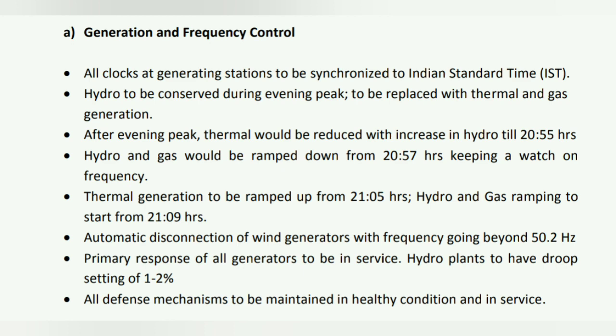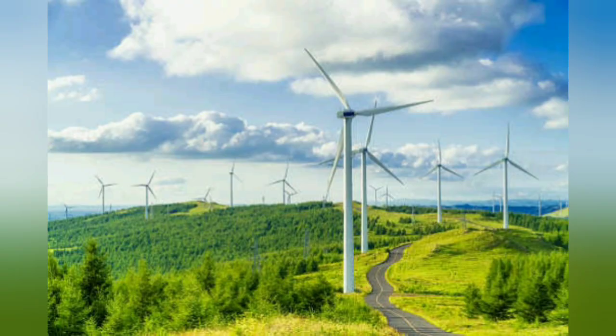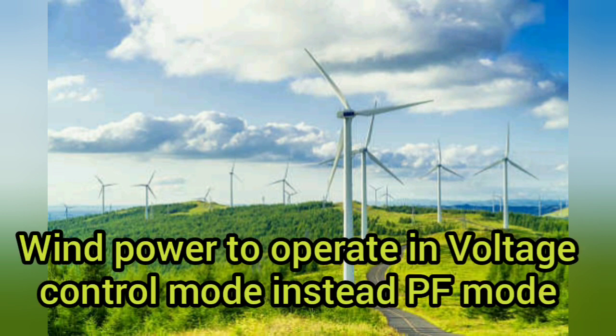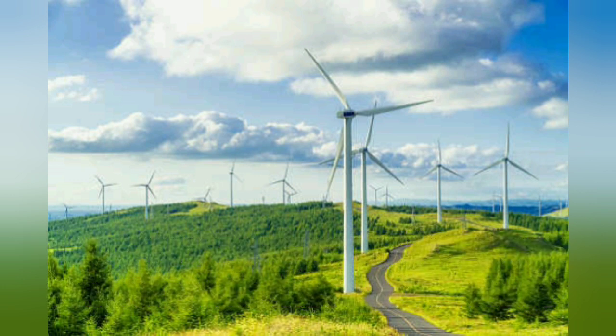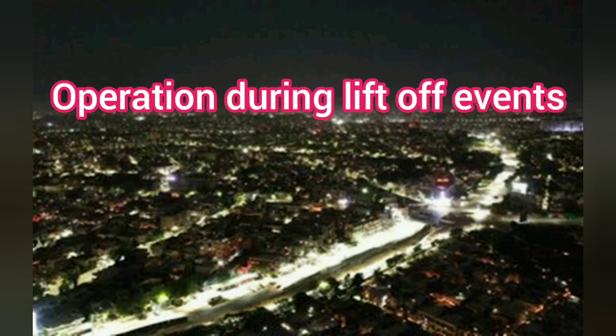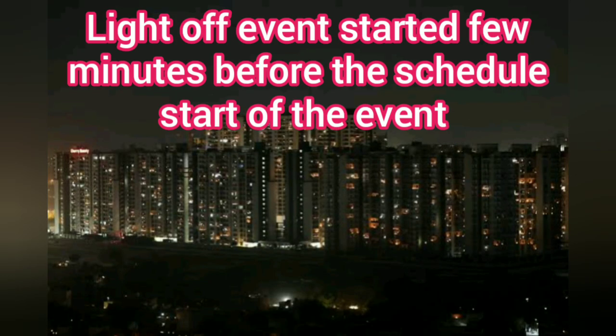All the generating plants were advised to absorb or generate reactive power as per the requirement. Wind turbine generators were advised to operate in voltage control mode instead of constant power factor mode. SLDC discoms were advised to switch off capacitor banks at distribution level. So these are the preparatory works that were done before the event. Now the operation during the lights-off event. Due to the diverse and distributed actions of households across the country, the effects of the event started a few minutes before the scheduled time of the event.